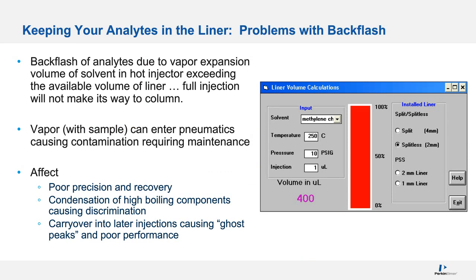Backflash can result when you have vapor expansion, because you're bringing 1 microliter of a solvent at room temperature to a very high temperature. So you get what's called vapor expansion. Water is probably the worst, but methylene chloride expands a lot as well. In this example of a 2 millimeter ID liner, that 1 microliter now expands to 400 microliters. Well, the volume of that liner is not 400 microliters. So where does our sample go? It goes outside of the liner.